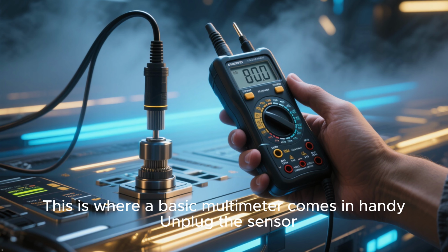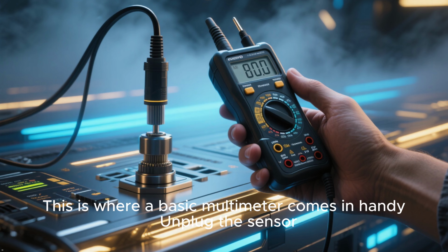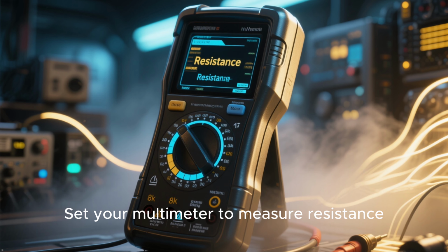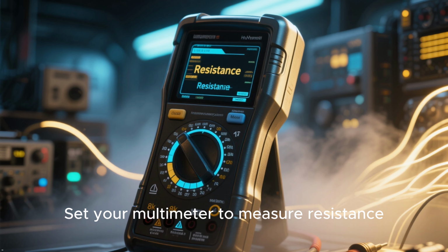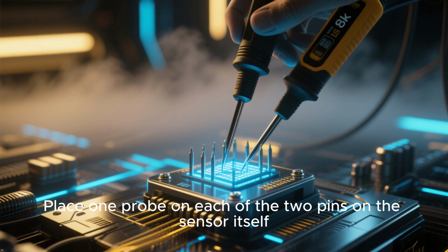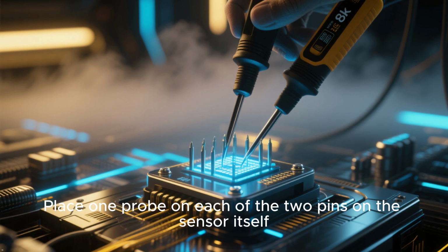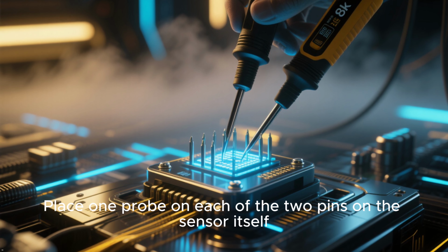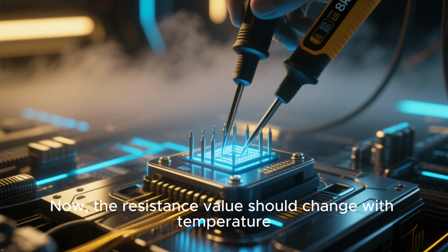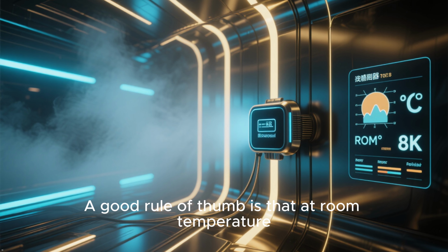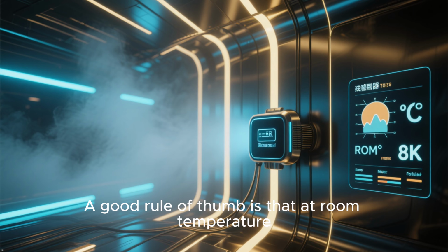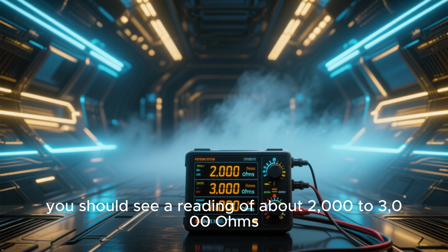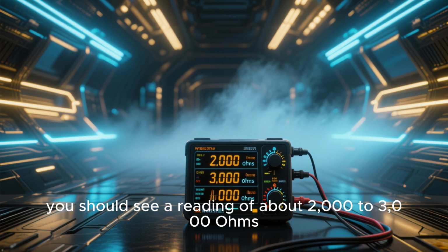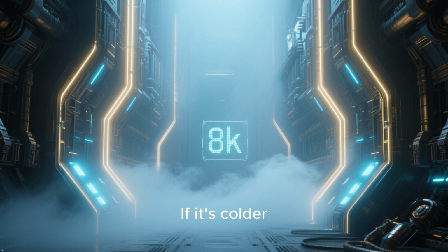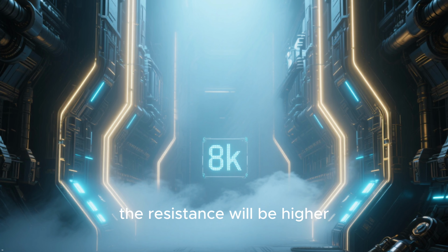If the wiring looks okay, the next step is to test the sensor. This is where a basic multimeter comes in handy. Unplug the sensor. Set your multimeter to measure resistance, or ohms. Place 1 probe on each of the 2 pins on the sensor itself. Now, the resistance value should change with temperature. A good rule of thumb is that at room temperature, around 70 degrees Fahrenheit, you should see a reading of about 2,000 to 3,000 ohms. If it's colder, the resistance will be higher. If it's hotter, the resistance will be lower.